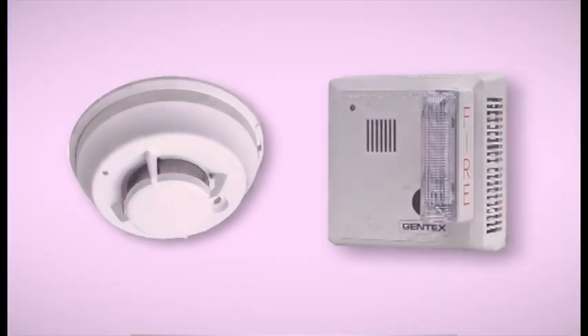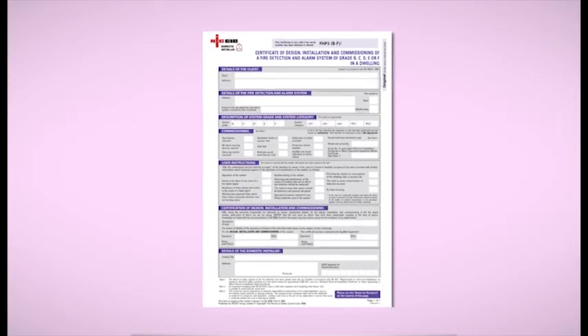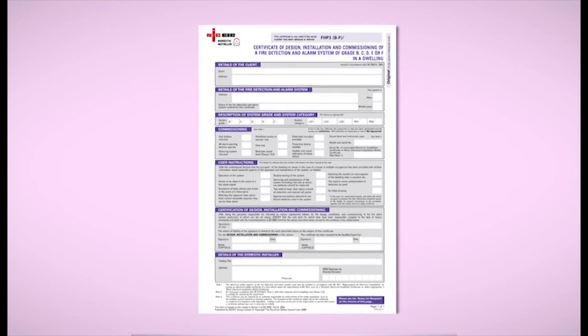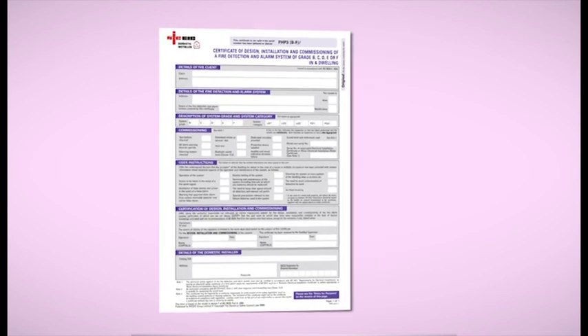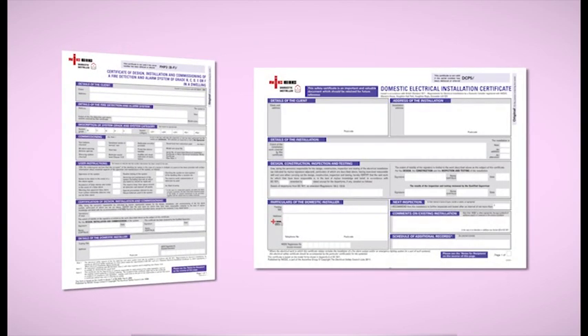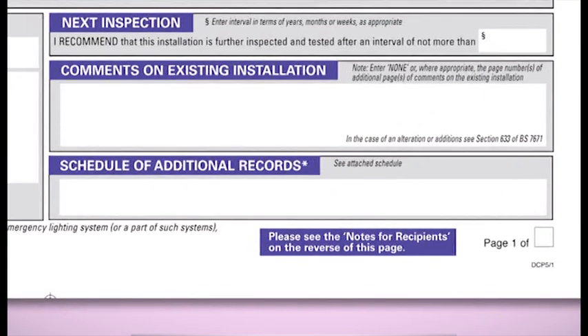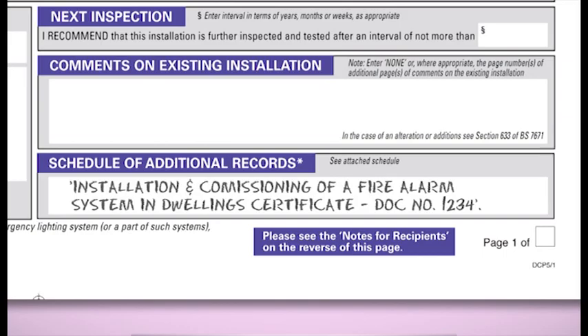Neither of these are used on their own to certify the commissioning of powered smoke and heat detectors. If you are installing these, then as well as the appropriate electrical certificate, you will have to issue an installation and commissioning of a fire alarm system in dwelling certificate to cover these devices. On the domestic electrical installation certificate, there's a box titled Schedule of Additional Records, where the details of additional certificates can be recorded. Let's move on to the electrical installation condition report.